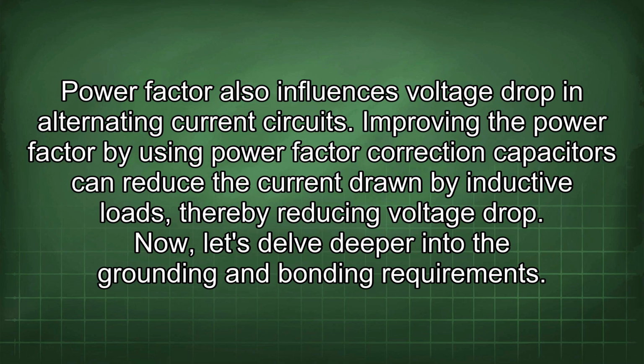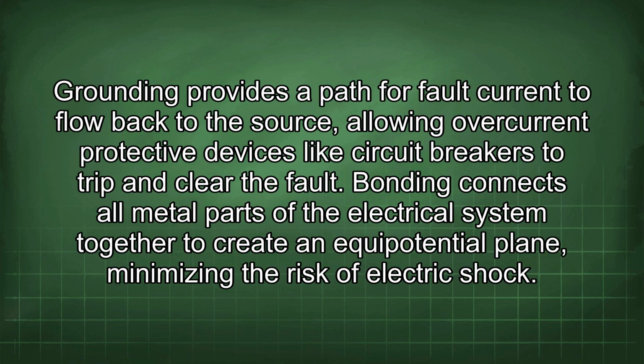Now let's delve deeper into the grounding and bonding requirements. Grounding provides a path for fault current to flow back to the source, allowing overcurrent protective devices like circuit breakers to trip and clear the fault.